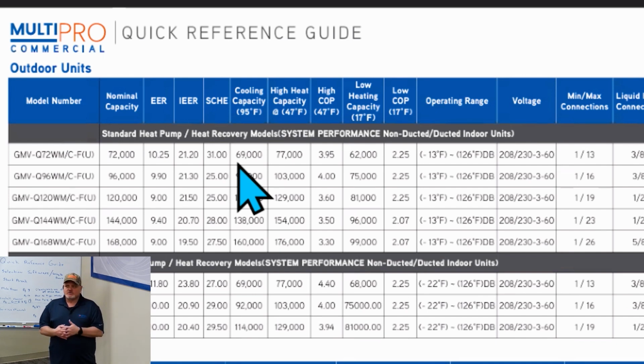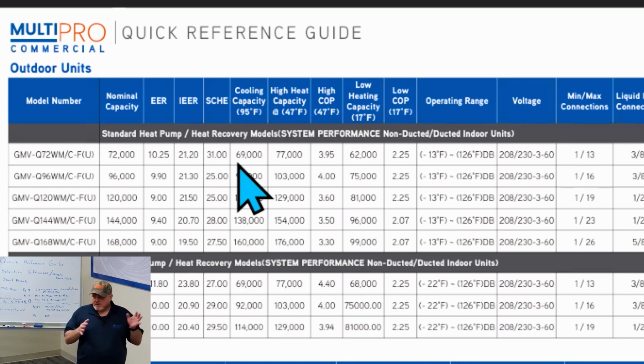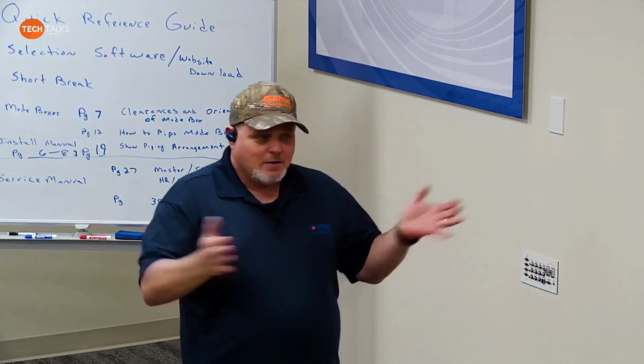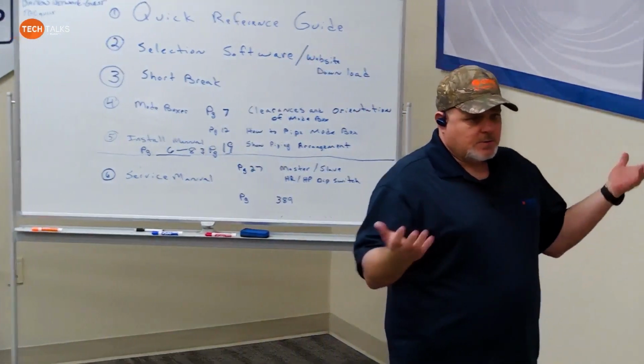I've had discussions with contractors in the field installing the single-phase multi unit in a residence with 4 or 5 indoor units. There's a big misconception - they think it's zoning, that they can have this one on heating and that one on cooling. Unfortunately, we don't offer heat recovery in single phase. But in office spaces and stuff like that, we can absolutely do that.